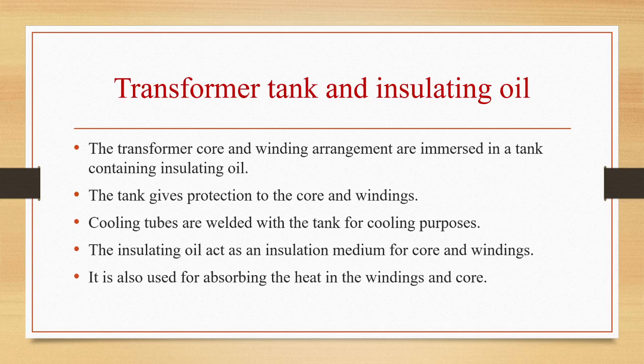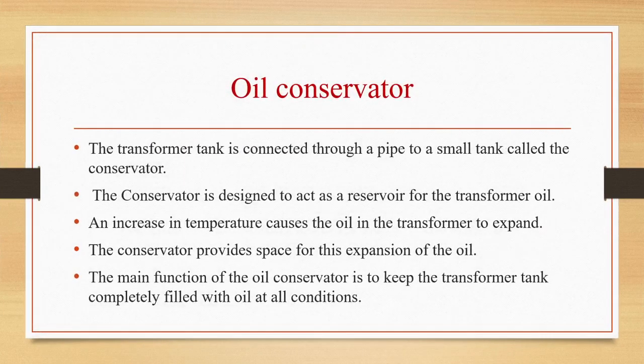So why is cooling required, and why is oil used here? First, oil will act as an insulation medium for the core and windings. Second, the oil will be used for absorbing the heat which is produced inside the windings and the core.